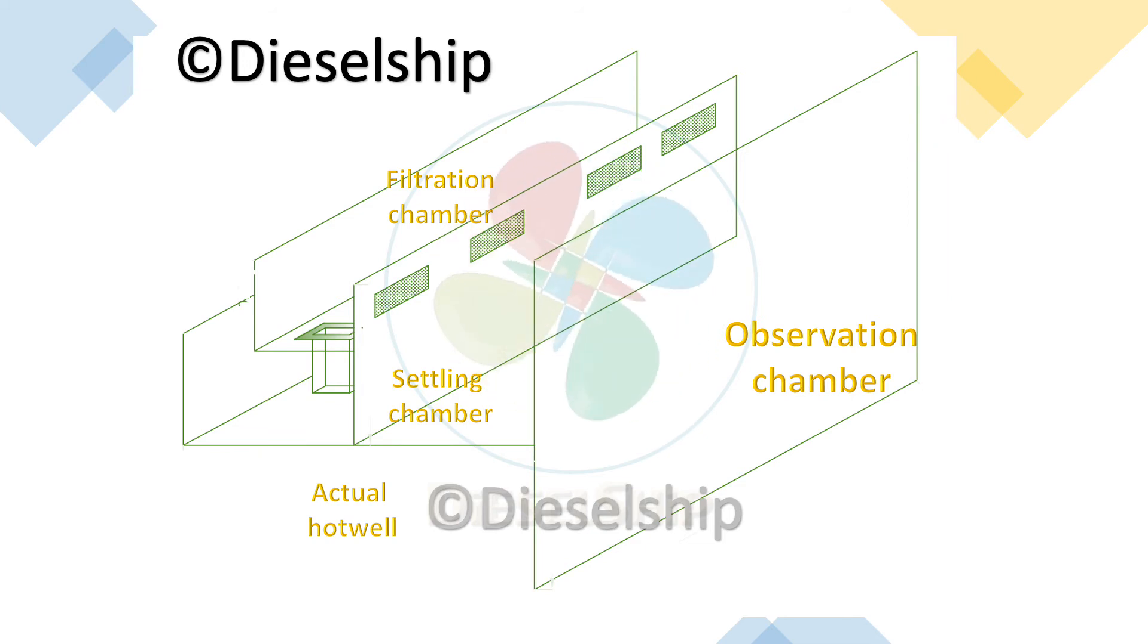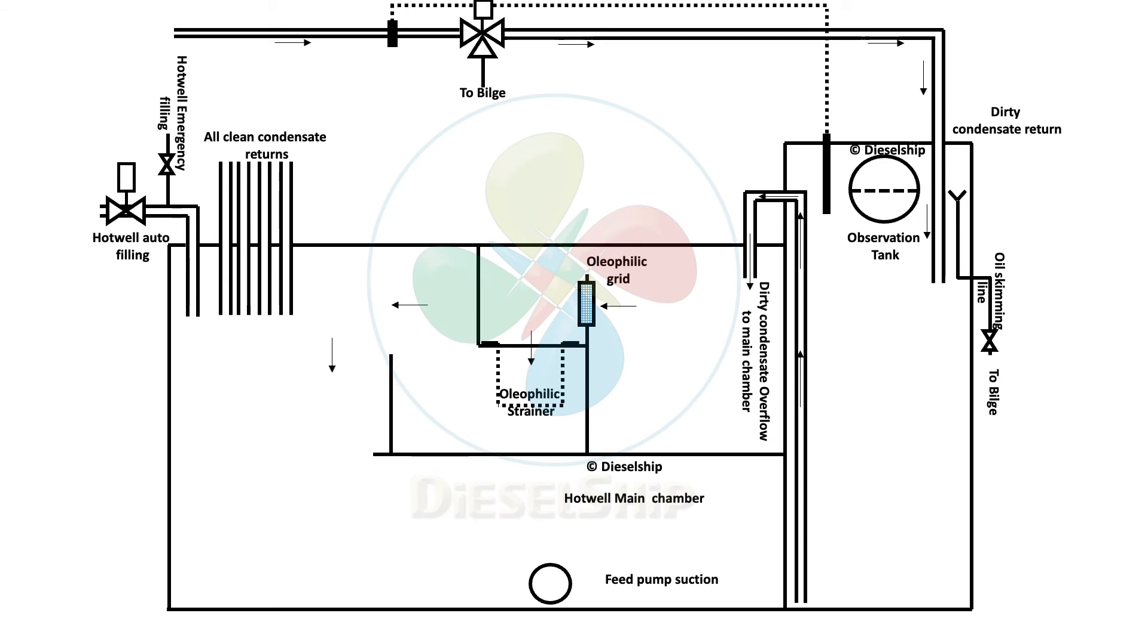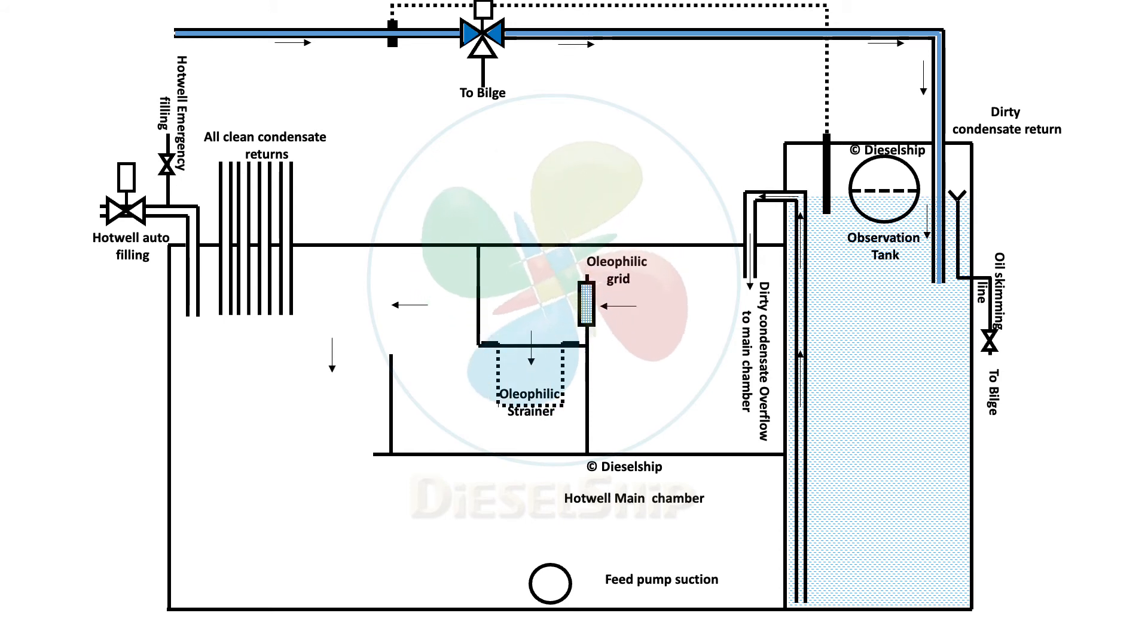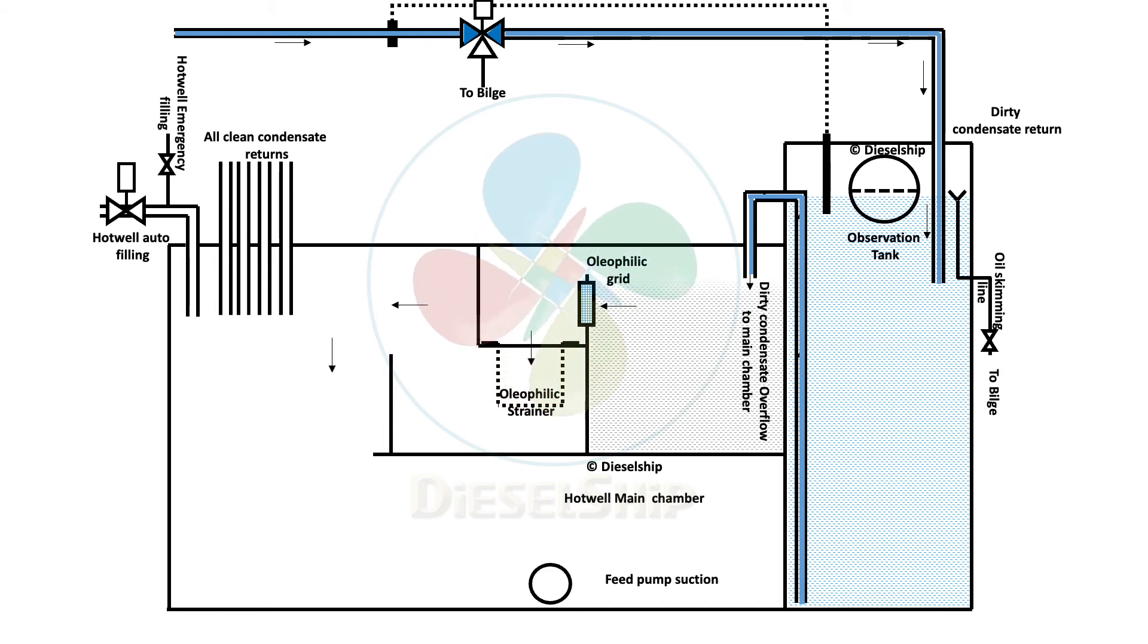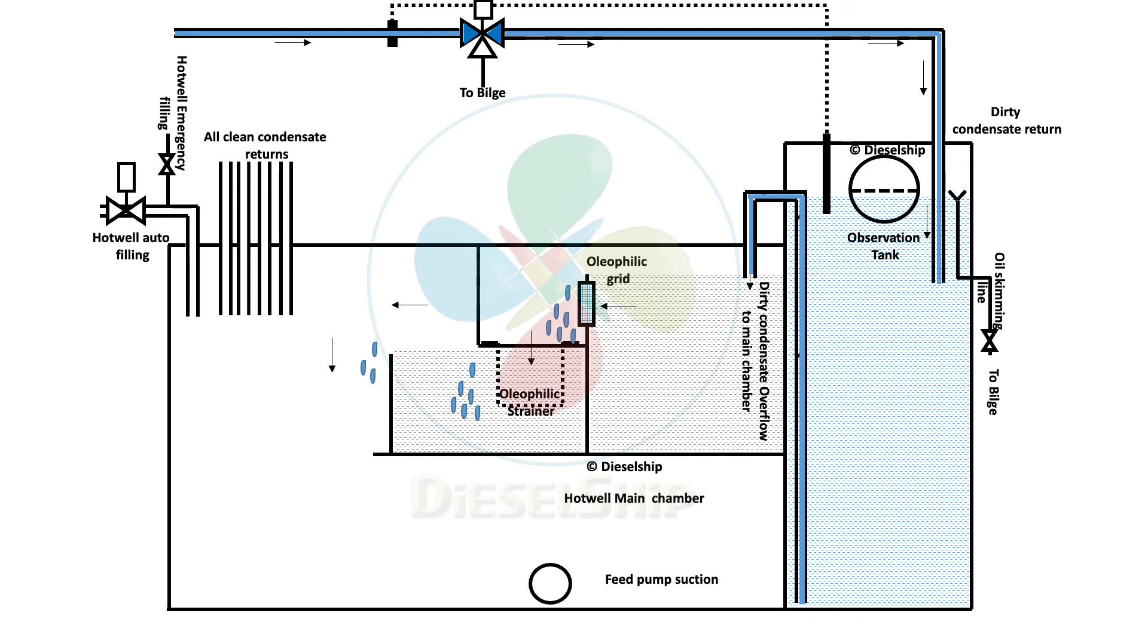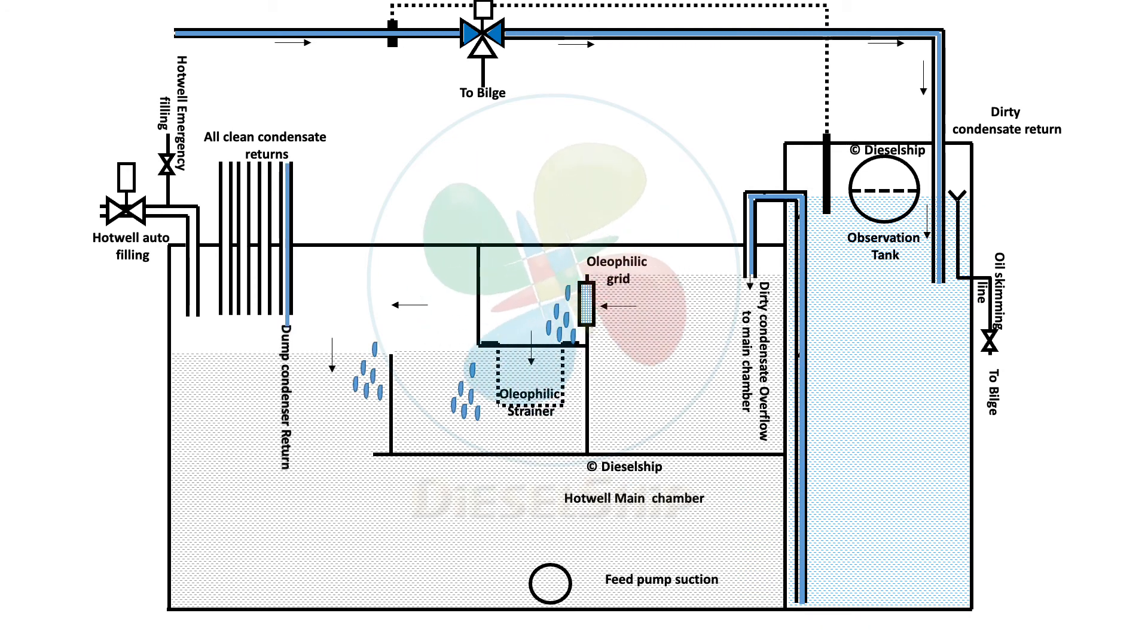The next slide is about the animation. You see the blue shade. The dirty condensate passes through the three-way valve, assuming there is no oil. It comes into the observation tank. Due to gravity, the water flows into the next chamber, which is the settling chamber. From here, it passes through the grids and then goes into the oleophilic strainer. From here, it fills up the filtration chamber. And then, the water will overflow into the main chamber, which is the hot well itself. These are the clean condensate from dump condenser, pools, galley, and they've operated.